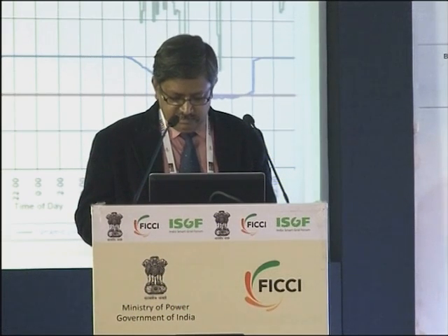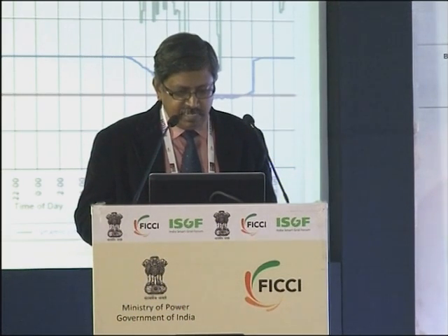Here is another example. The green lines are the dynamic line rating of the line at any time, which is actually computed. The red one is the static rating, and the blue one is what we call the ambient adjusted rating. So it's a slightly less safe, more aggressive rating of the line, and you can stretch the line to that level if there is a need, as it arises.